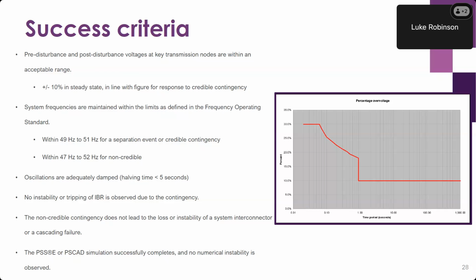For oscillations in the system, we want adequate damping. The halving time of any oscillation should be less than 10 seconds, but to account for planning and operating uncertainties, we aim to achieve a halving time of less than 5 seconds. We're also looking at the performance of the generators, including fault ride-through capability of the IBR units and distributed PV disconnections. To be successful, we don't want the loss or instability of any interconnectors. We don't want to see any cascading failures, and we want all emergency frequency control schemes to operate as intended. We're also looking to ensure the PSSE or PSCAD simulation successfully completes.